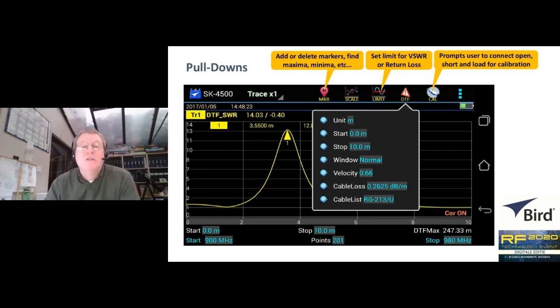We can also manually enter these details. If we click on the word velocity, we can type the precise number, and the same for the cable loss characteristics. Or we could edit the database to add an entirely new cable that the system doesn't already know about. The menu also allows us to specify the range of the horizontal distance axis. In this case, 0 to 10 meters. There's obviously no point in having several hundred meters of horizontal range on the x-axis if the cable's only a few meters long. So we can specify those limits, and you'll notice at the top of the screen, unit is set to m, meters. It gives us the opportunity to specify either metric or imperial units, feet.